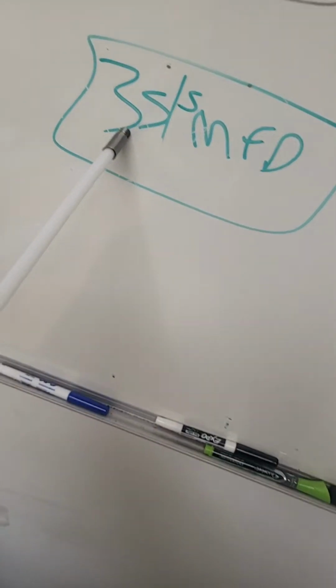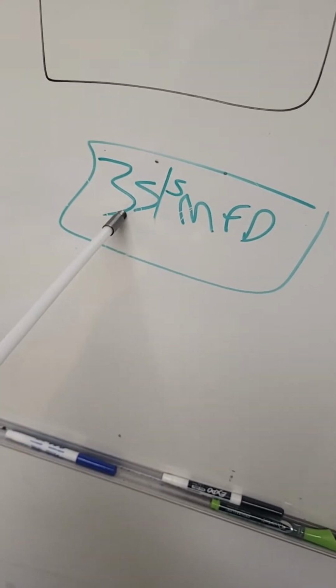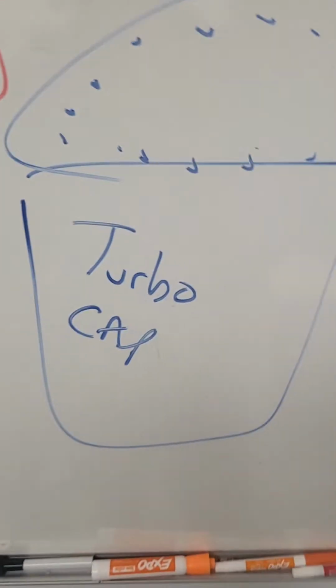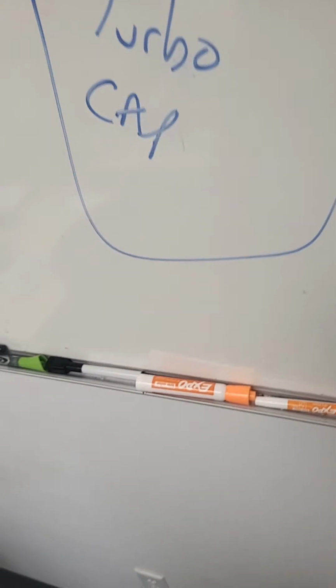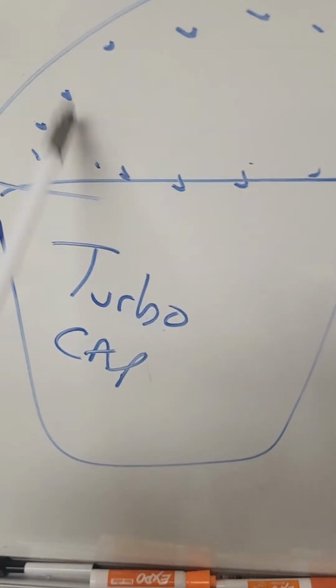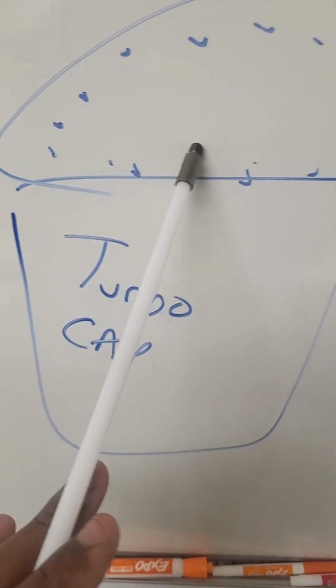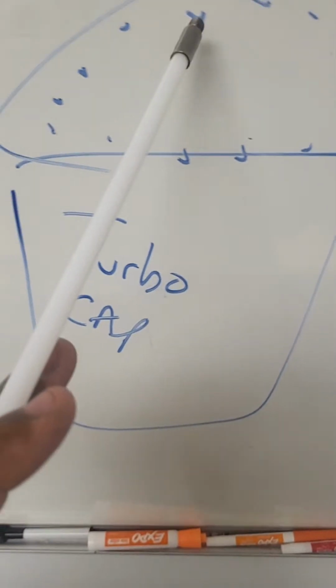In this scenario, guys, if you know you don't have any standard 35-5 dual caps, you should stick with your turbo cap. It's more expensive at the time, but can it get the customer up and going? Most importantly, guys, a 35-5 turbo cap, if you bridge the jumpers correctly, will still work the same way.